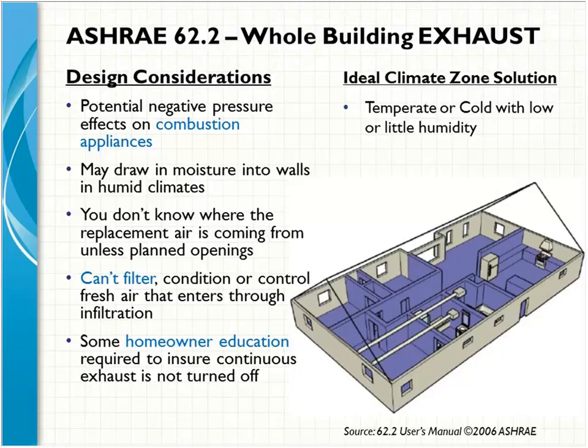Another criticism of the exhaust-only ventilation approach would be that the air is not filtered. You can't filter it like you would in a supply ventilation system, where you're pulling it in through a duct and running it across the furnace filter before it's delivered to the home. And that's true. And you don't know where that air is coming in through the building shell. Chances are it's coming in through the openings in the building shell closest to where the fan is. And if that's a crawl space or an attic hatch, or someplace where there might be undesirable air, you certainly could be dragging things in from those spaces that you don't want in your home as well. So those are some of the negatives to the exhaust-only approach.